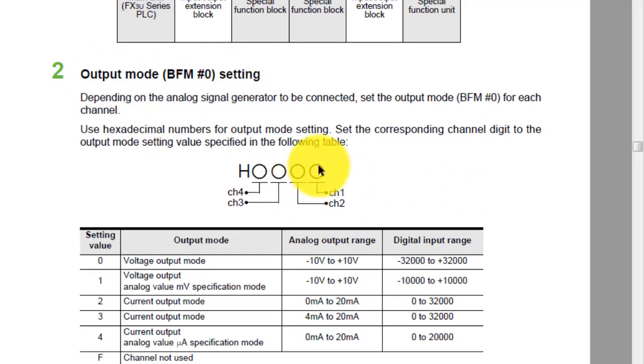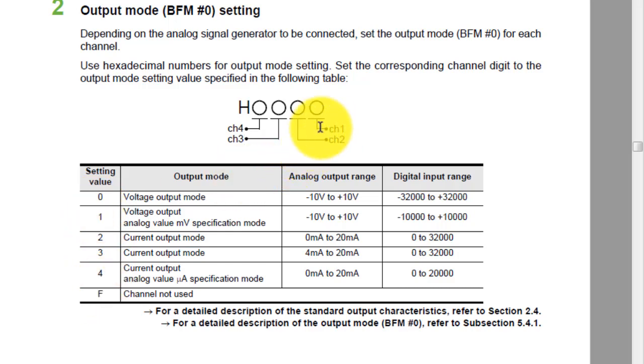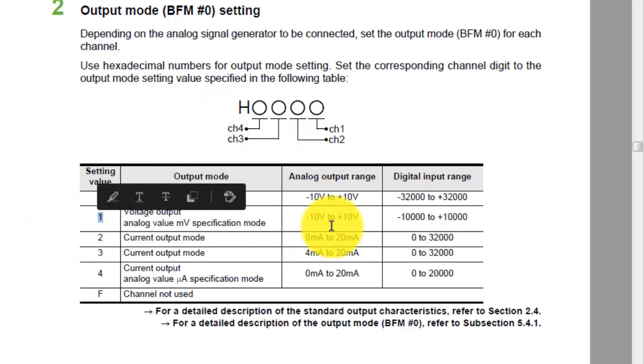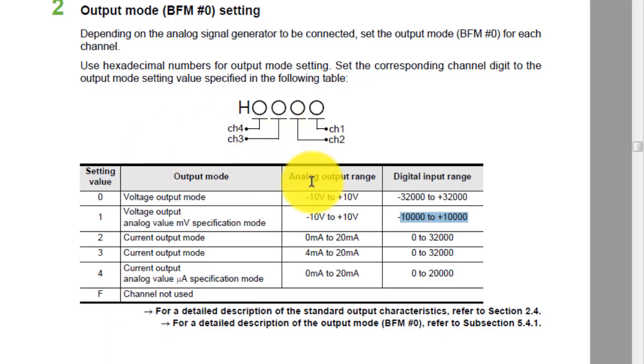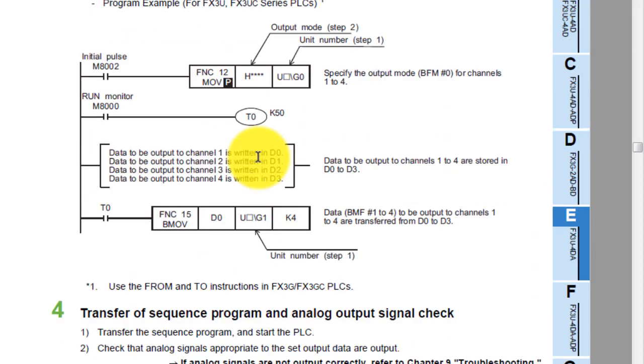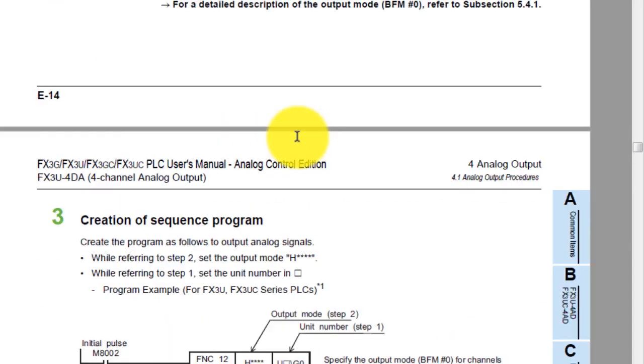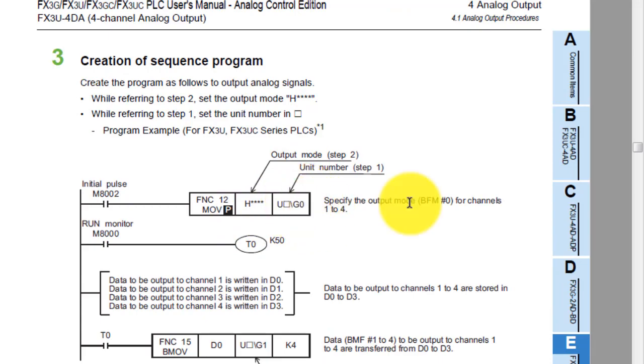These output mode settings are very important. You can see the hexadecimal values for each channel. If you put 0 in channel number 2, you will use voltage output minus 10V to plus 10V. If you use value mode 1, it will be the same range but the digital input value changes. If you put the value F in any channel, that channel will not be used. The MOV command is used to move your setting into buffer memory number 0.